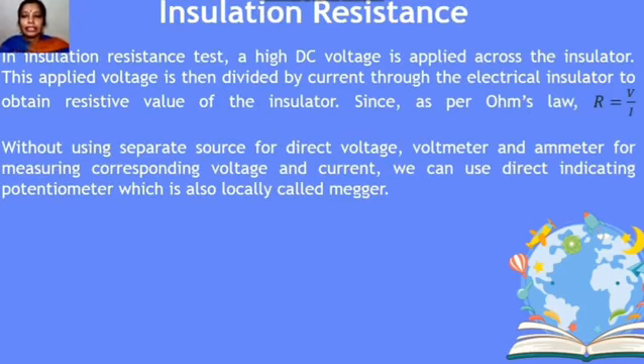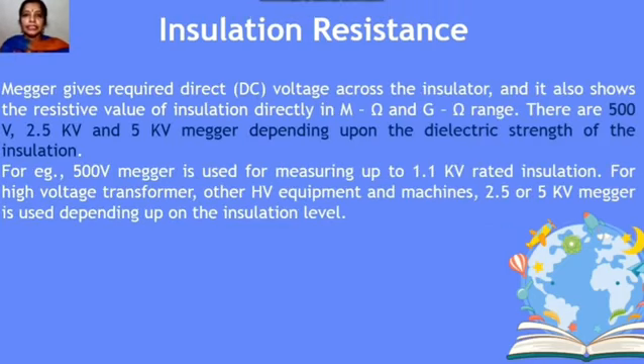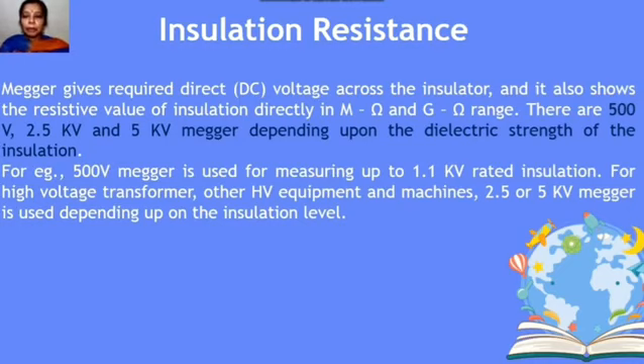A megger applies a direct DC voltage across the insulator, where the resistive value ranges from megaohms to gigaohms. There are many types of meggers available: 500 V megger, 2.5 kV megger, and 5 kV megger, depending upon the dielectric strength of the material being tested. For example, a 500 V megger is used for measuring up to 1.1 kV rated insulation, while 2.5 or 5 kV meggers are used for high voltage transformers and other HV equipment.